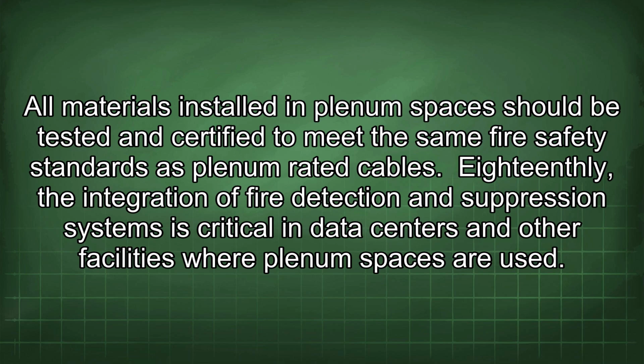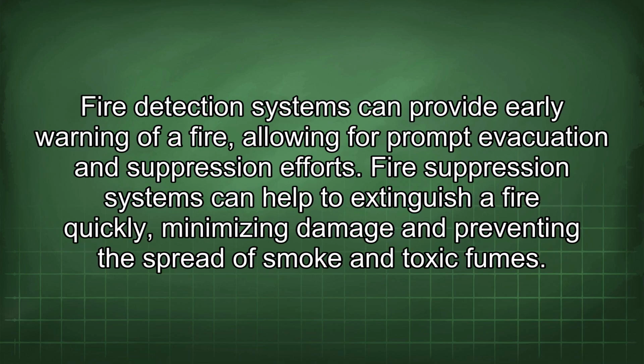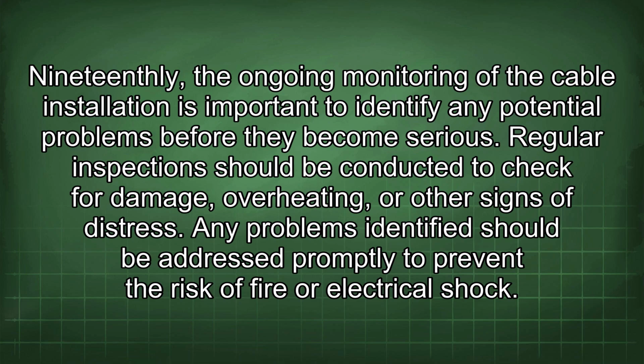Plenum spaces are used. Fire detection systems can provide early warning of a fire, allowing for prompt evacuation and suppression efforts. Fire suppression systems can help to extinguish a fire quickly, minimizing damage and preventing the spread of smoke and toxic fumes. 19thly, the ongoing monitoring of the cable installation is important to identify any potential problems before they become serious. Regular inspections should be conducted to check for damage, overheating, or other signs of distress. Any problems identified should be addressed promptly to prevent the risk of fire or electrical shock.